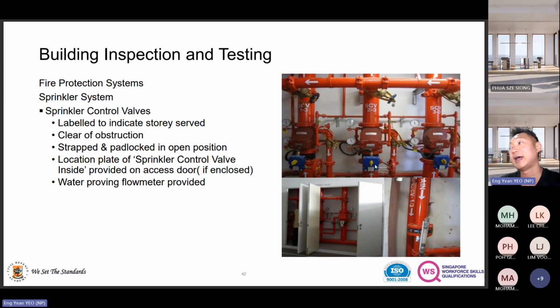So when we do the additional stuff, for example just a visual check, we make the necessary recommendation and ask them to look into it, provided the fire protection vendor gets into the picture to find out what happened and troubleshoot it, because that's their system. I'm here to give a high-level overview, suspecting, hey, this one may be out of calibration. You need to calibrate it again, or you need to replace it. All right. So make sure it is clear of obstruction, especially in those risers.